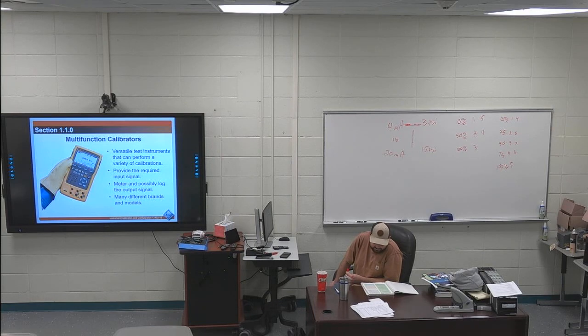Calibration defined, second paragraph, from the beginning all the way through the sentence that has the multifunction loop calibrator in it. Calibration involves proportionally matching the output signal or level of energy to the input signal or level of energy. This can be accomplished by using loop calibration test equipment that provides a variable energy source to the instrument's input, while a second device reads the output signal using an appropriate meter. Calibration can also be done using a multifunction loop calibrator, which provides the energy source and measuring capabilities in a single unit.